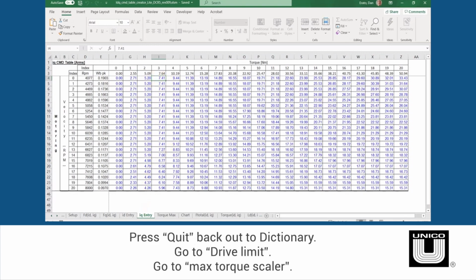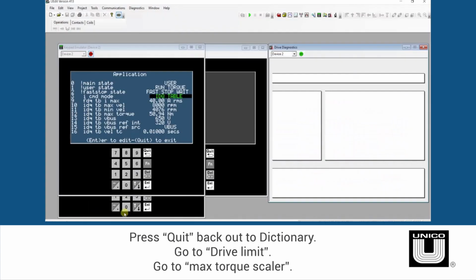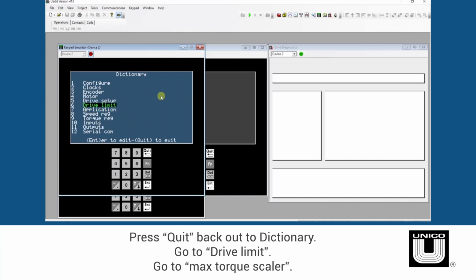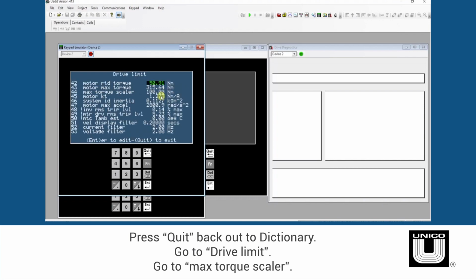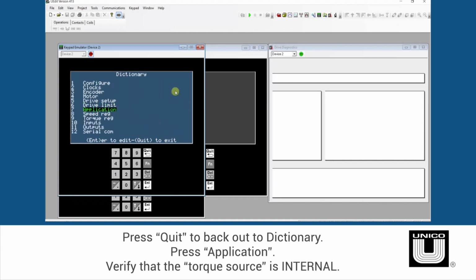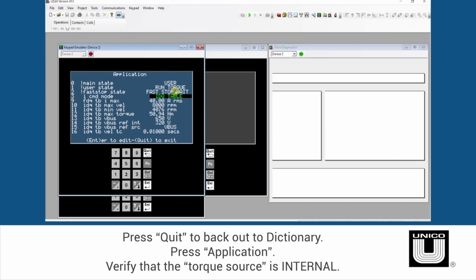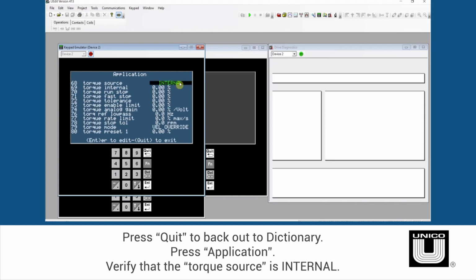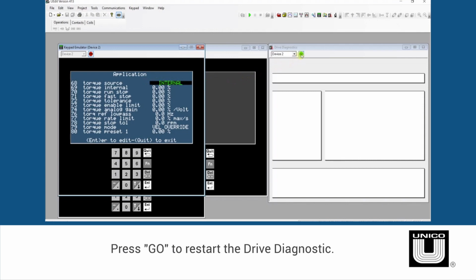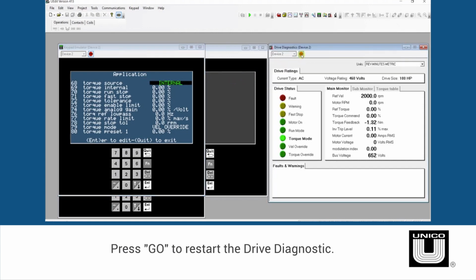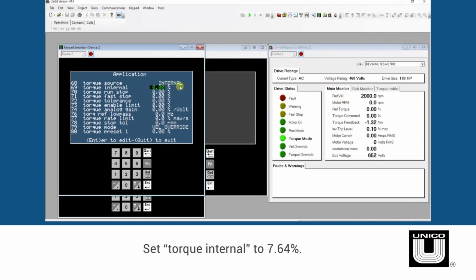Before providing a torque reference for the drive, verify the max torque scalar. To do this, go to Dictionary, Drive Limit, and find the parameter called max torque scalar. This is 100 Newton meters for this drive. Next, go to Dictionary, Application, and verify that the torque source is internal. Set torque internal equal to 7.64%, which will correspond to 7.64 Newton meters.